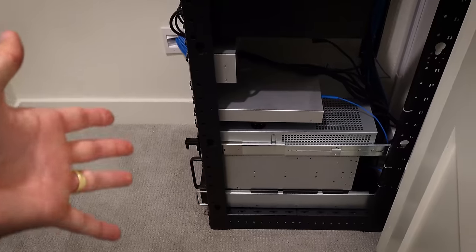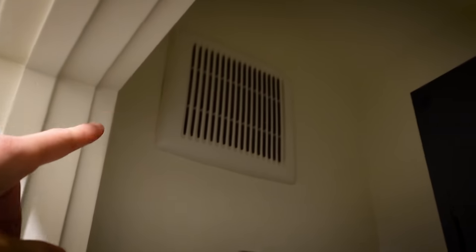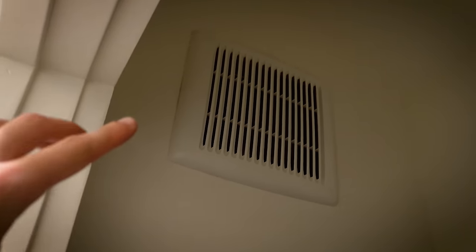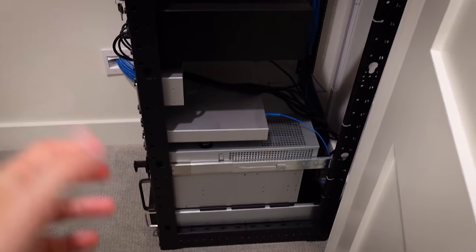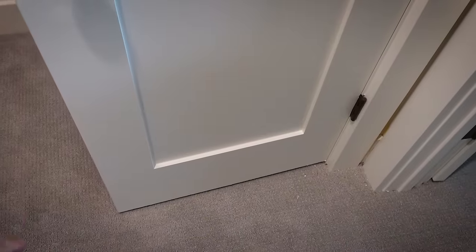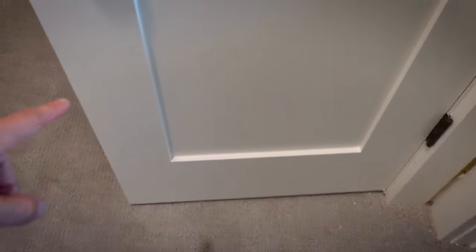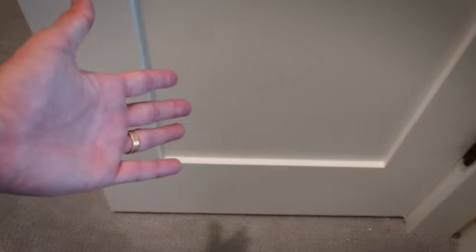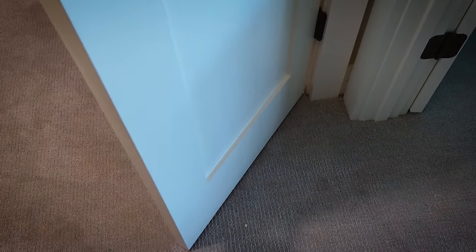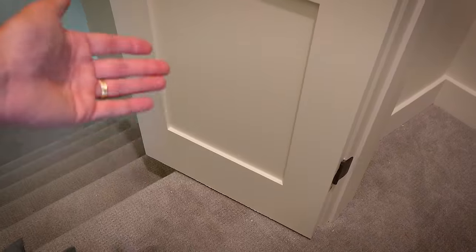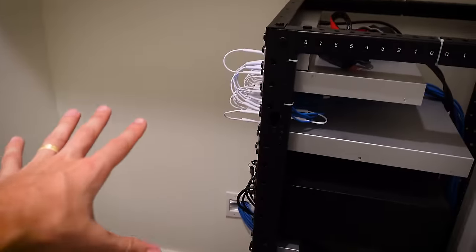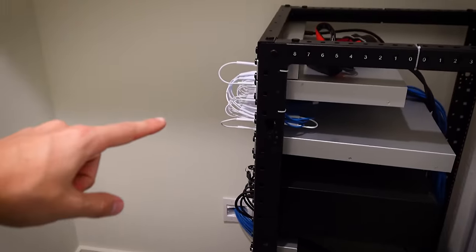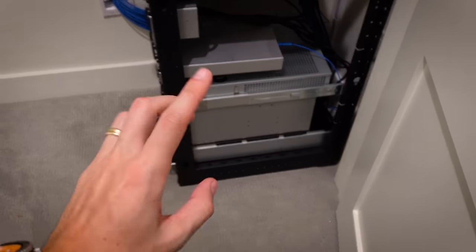While we're waiting, something else to note. I actually did mention this in the first or second server video we uploaded that some of you didn't see. I do have active ventilation in this closet. I know it's a small space for all this stuff to be in and I still have to modify the doors because there's no way for fresh air to get in yet. What I'm going to do is probably cut out a couple sections down below on each door for just small passive vents so that there's no build up of negative pressure inside here. That hot air is going to rise and escape out the vent and then fresh air will come in through the door down below into the servers.